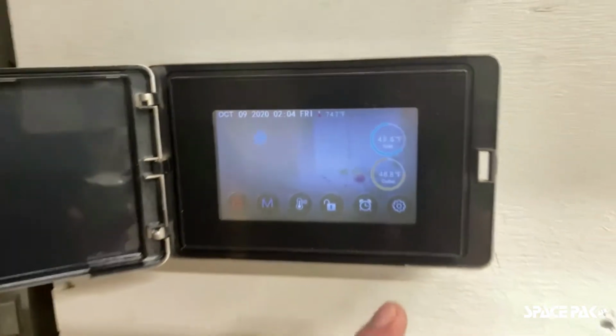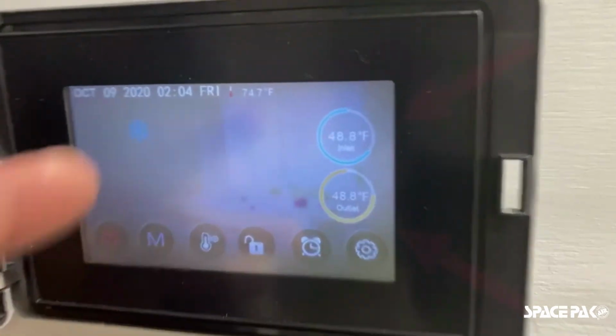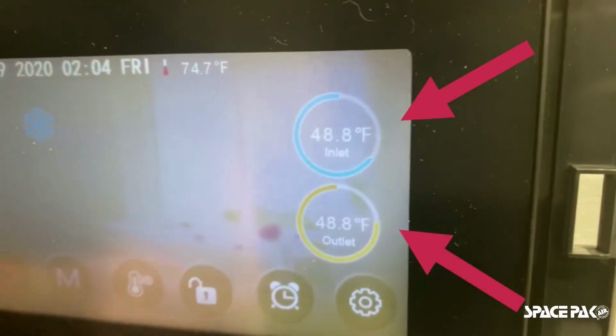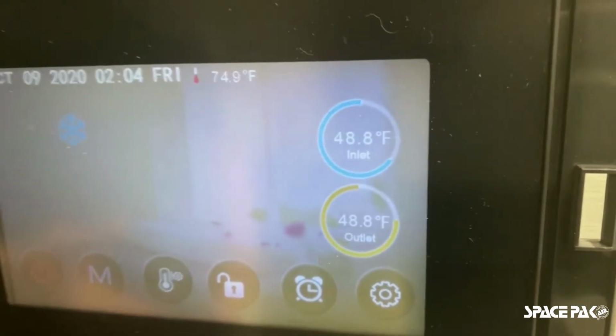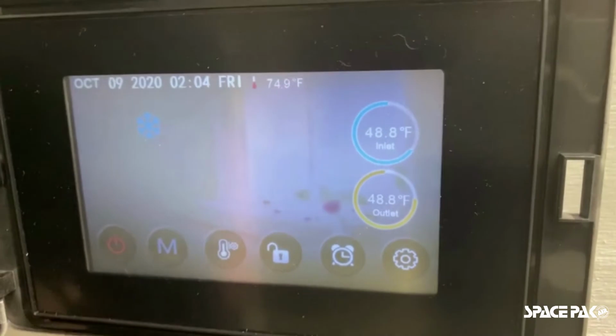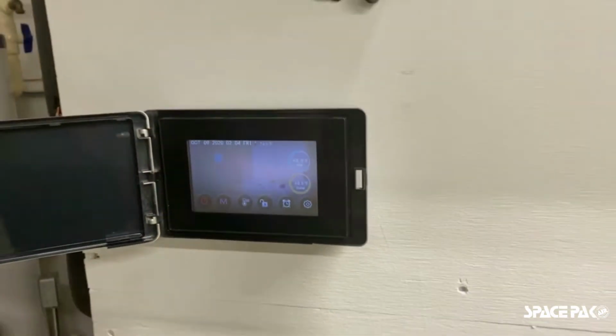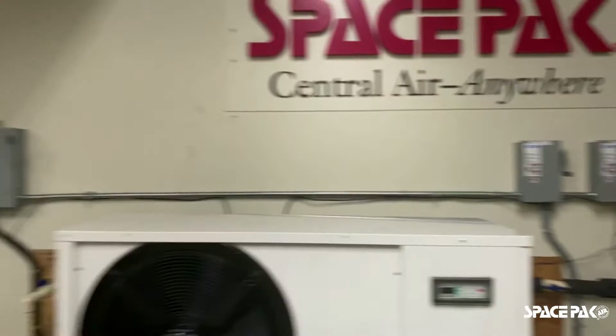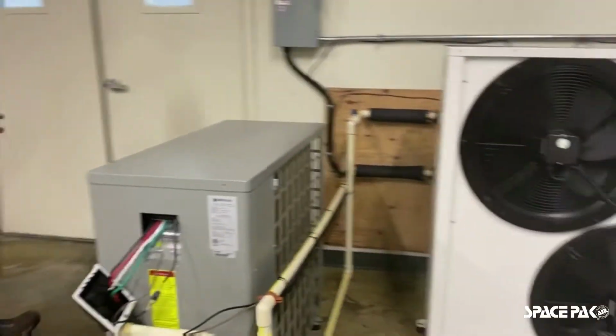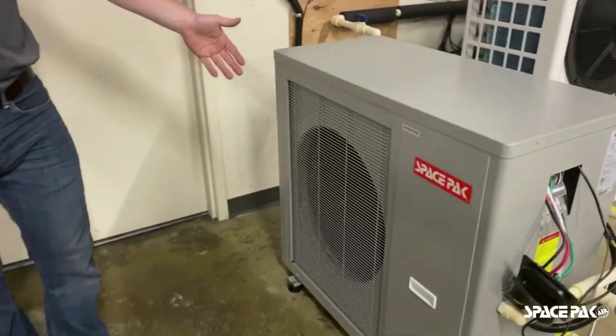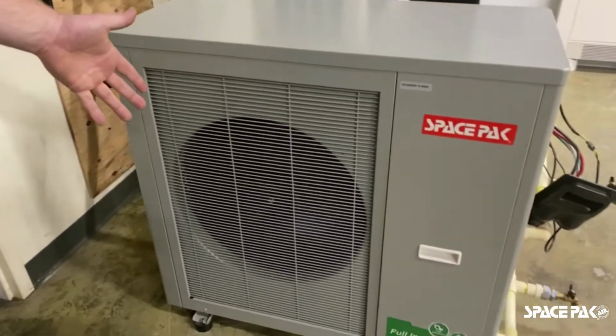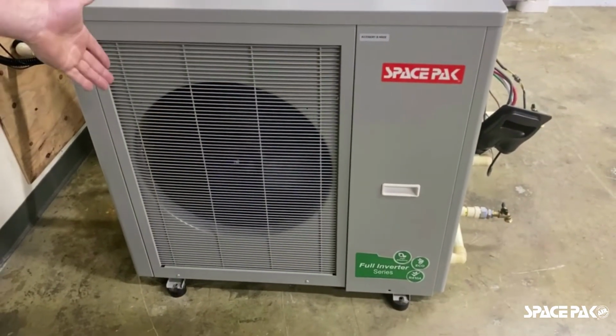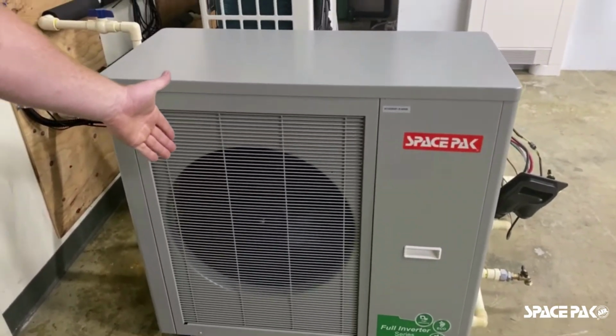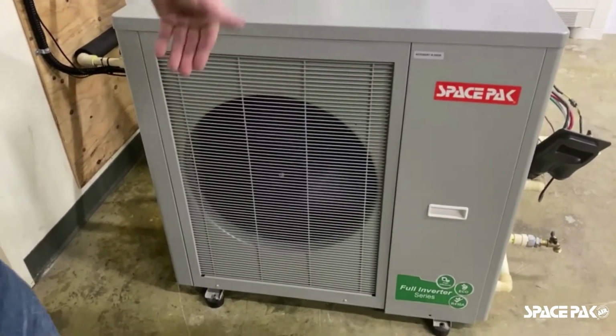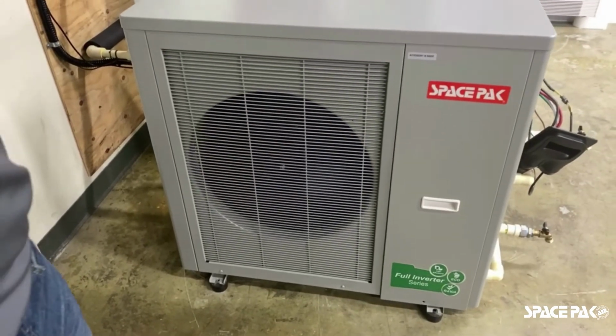To the right side of the screen, we can see that our inlet and outlet water temperatures are being displayed, both of the same temperature, okay, because we've started circulating water. However, we have not turned on the compressor yet. If we take a walk a couple steps back to the unit, we can actually see that the fan is running, okay. If you cannot particularly see that, feel free to just assume that we're telling you the truth. Fan is running. We're currently running the circulator to prove flow.